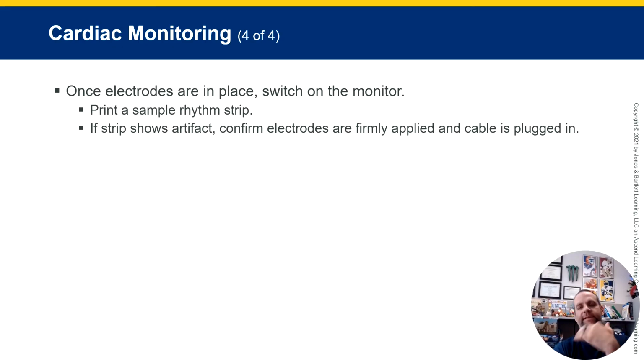Now, once the electrodes are in place, it's time to actually check your work. Turn on the monitor, run a short strip, and again, look for clean, steady lines, right? So if you see a lot of squiggles or interruptions, troubleshoot. Check the loose cables, poor adhesion. Maybe the patient was moving. So don't underestimate how much accurate monitoring matters, right? A good tracing can really help receiving teams identify a STEMI, which means faster interventions and better outcomes. Whereas a bad tracing can delay decisions or even lead to misinterpretation.